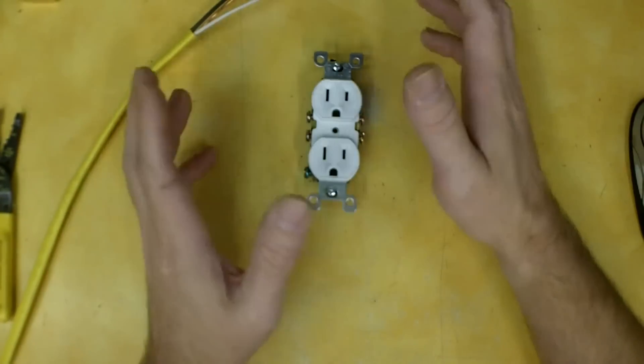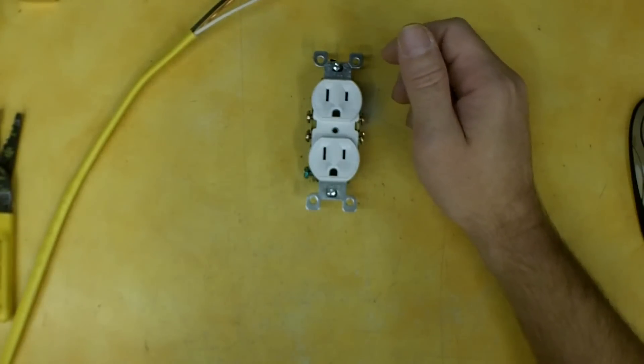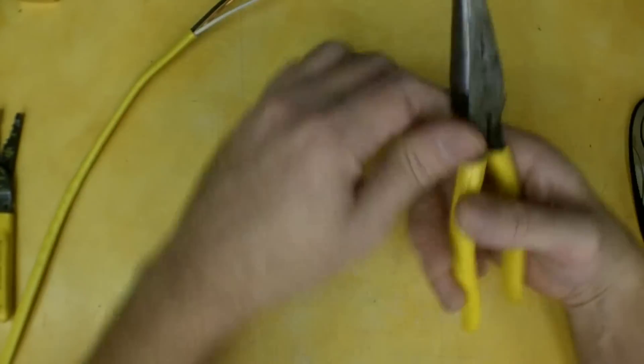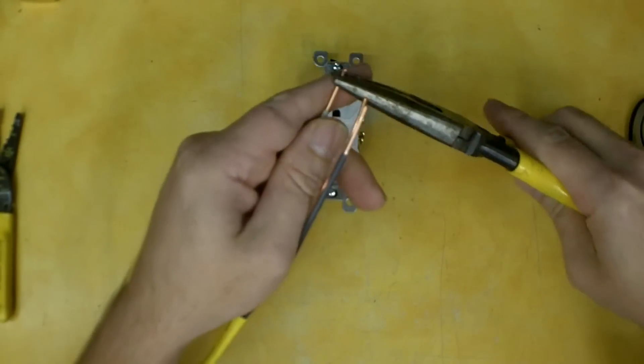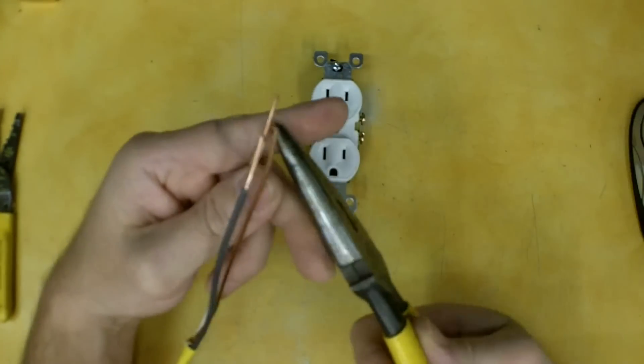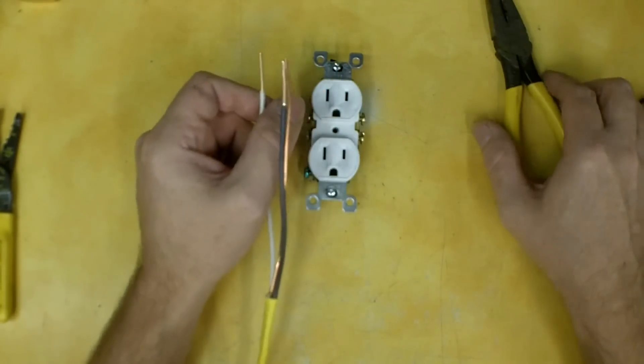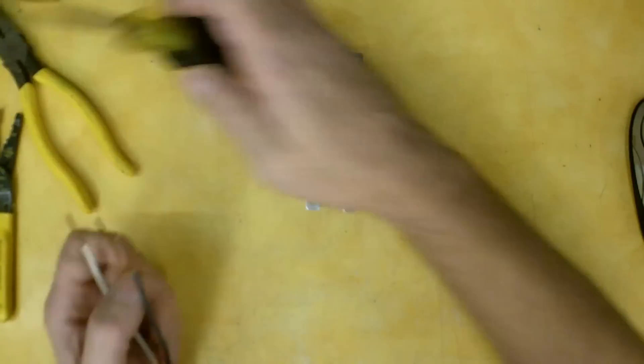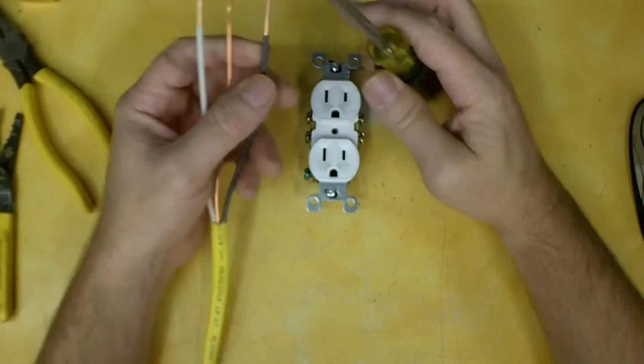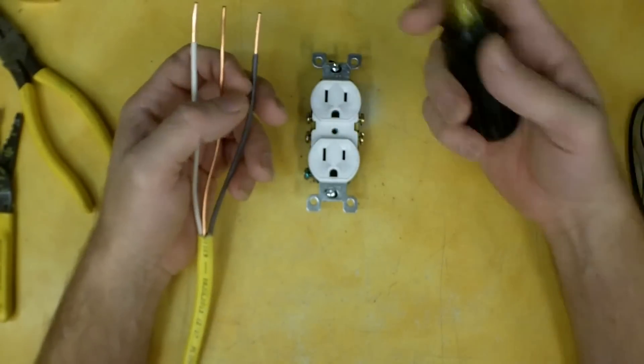And if you are going to put them in the back, which I would say a big no-no, always run your screws in if you're doing it that way. Just run them in. You still have to wrap the ground anyway. But there's a couple of different ways to do this. And one, what a lot of electricians will do is they'll just use their needle nose and they'll come in and they'll turn their horseshoe on this and then put it on.